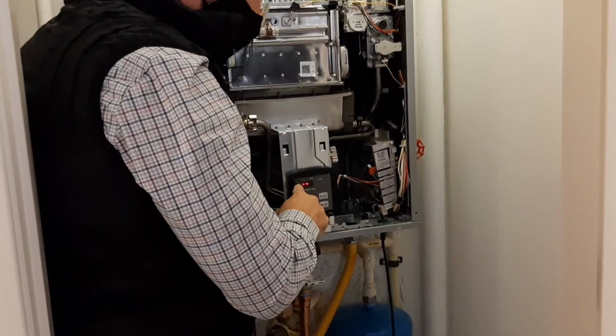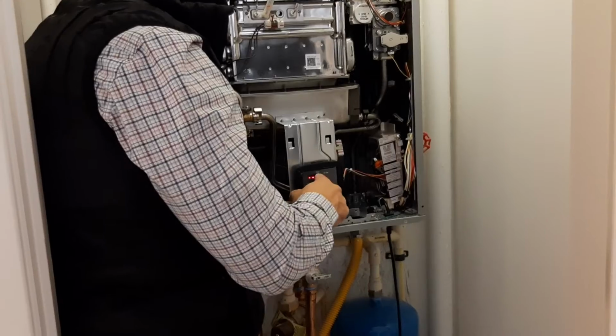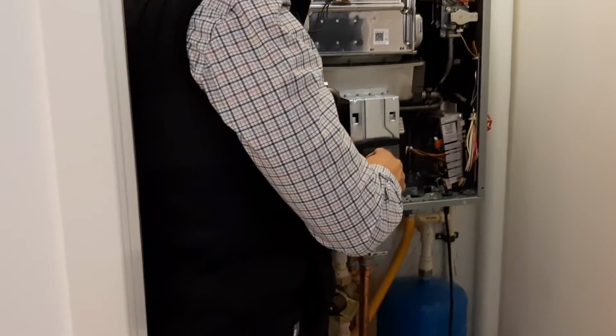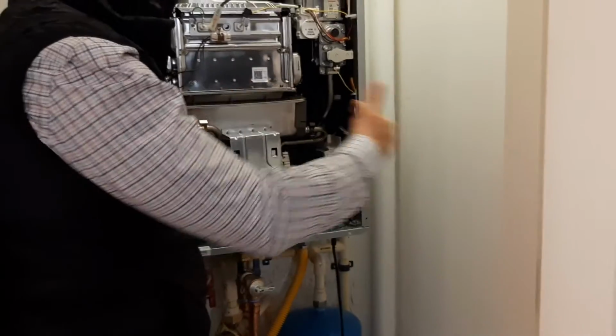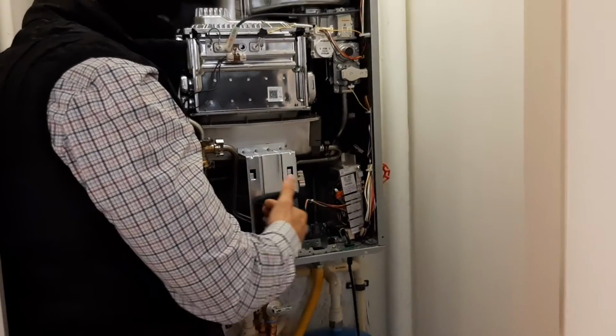It'll save up to 2 of the same error code in a row. So if it said 1 and 11, and then 2 and 11, and then 3 was dash dash, that means you could have had 1,000 11s. It's only going to save 2 because it doesn't want to wipe the rest of the history.